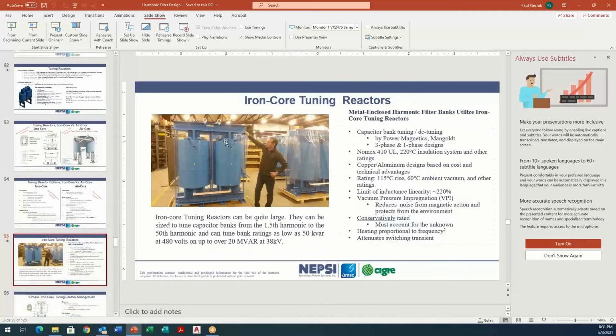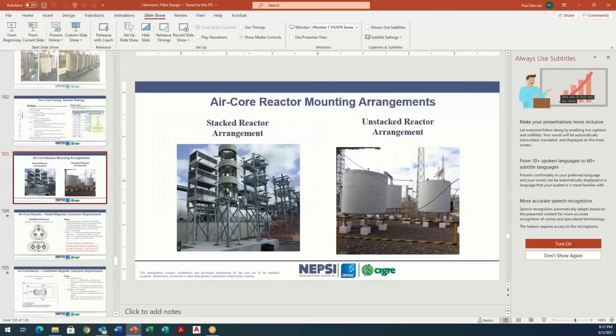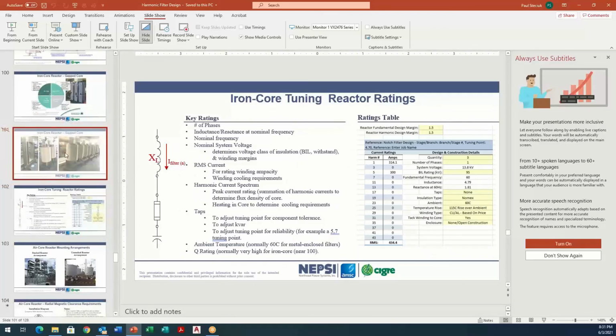Yeah, well, think about this. We built an enclosure around that reactor, and now you determine that the reactor needs to be bigger. Well, there's no space for it, right? So redesigning a whole plant, you could potentially be doing it, and then you have the cost to pull this out of an enclosure. If it's an air core reactor, you're going into it. So even this one here, if the reactor got to be bigger, it would start to interfere with the adjacent components. So you now have field work versus factory work, and it's very expensive. And you have, of course, the downtime of the facility that we did your miscalculation at.